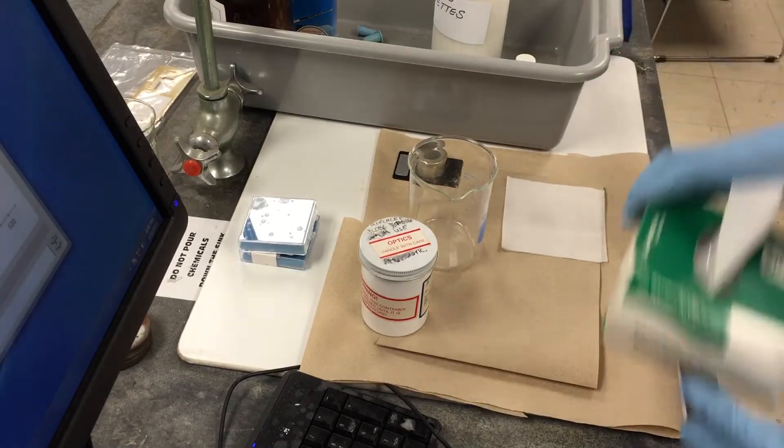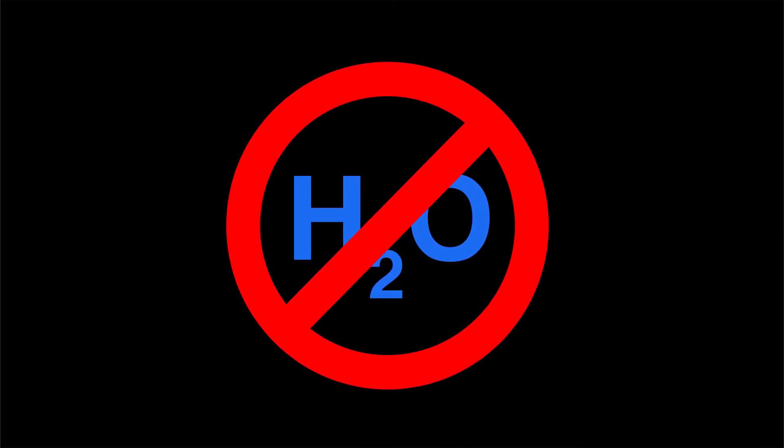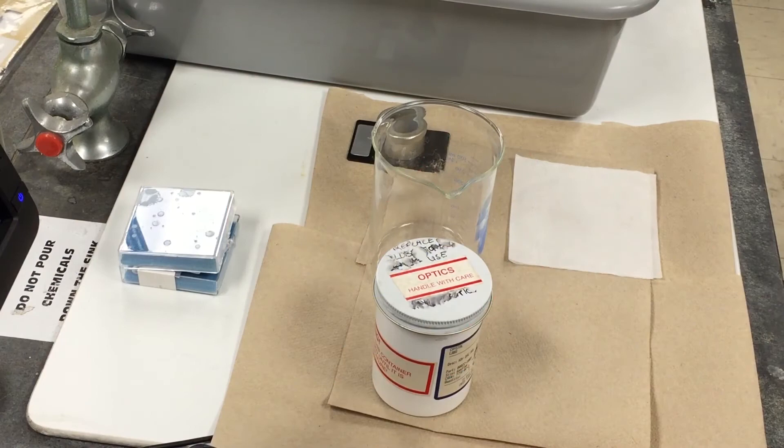Keep in mind, the salt plates we use are fragile and expensive. Water will damage them. We keep the plates in a closed container with silica gel desiccant.